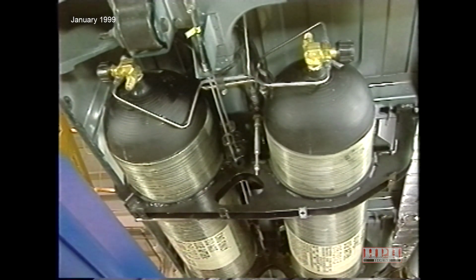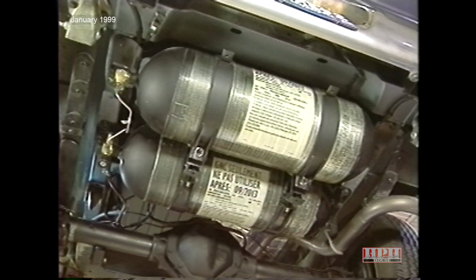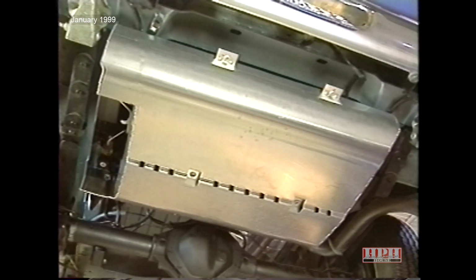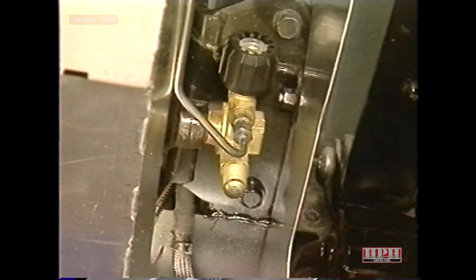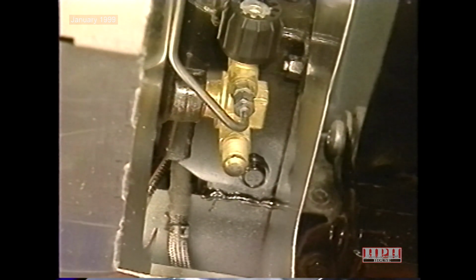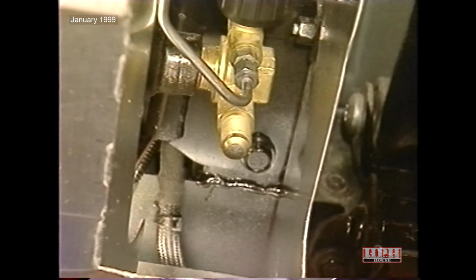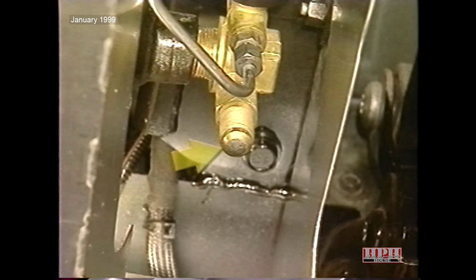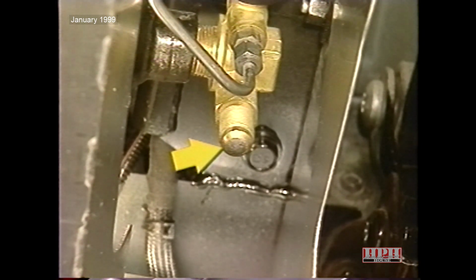Speaking of which, now 4 fuel cylinders or containers, as described in the CNG Owner's Manual Supplement, are standard equipment. 2 are positioned under the driver's side of the vehicle, while 2 are mounted behind the rear axle under the vehicle. A shield is used to protect the cylinders. Each fuel cylinder has its own black-handled multi-turn shutoff valve, which is used to stop fuel flow from the cylinder for servicing the fuel lines and fittings. Each cylinder also has a pressure relief device that automatically opens if the temperature rises above 217 degrees Fahrenheit. Keep in mind that once pressure is released, the device will need to be replaced and the cylinder re-inspected.